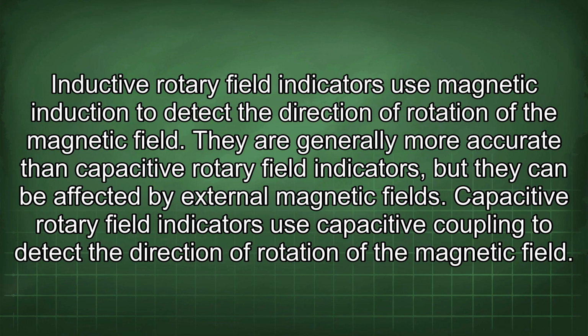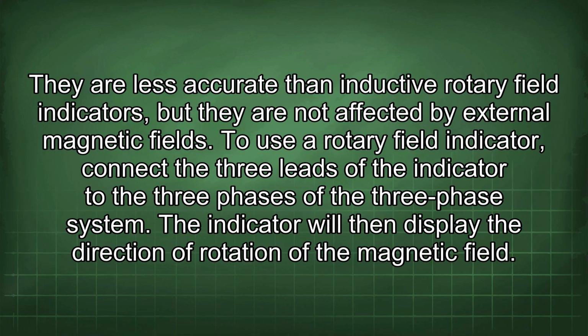Inductive rotary field indicators use magnetic induction to detect the direction of rotation of the magnetic field. They are generally more accurate than capacitive rotary field indicators, but they can be affected by external magnetic fields. Capacitive rotary field indicators use capacitive coupling to detect the direction of rotation of the magnetic field. They are less accurate than inductive rotary field indicators, but they are not affected by external magnetic fields.